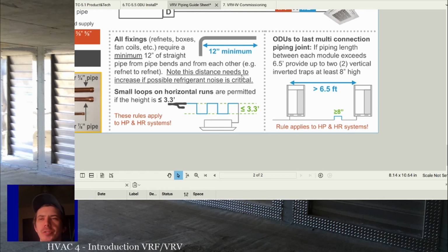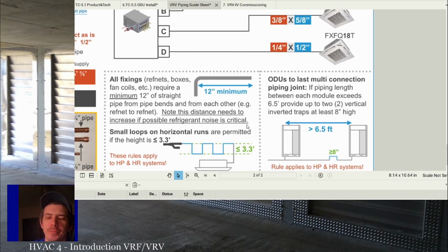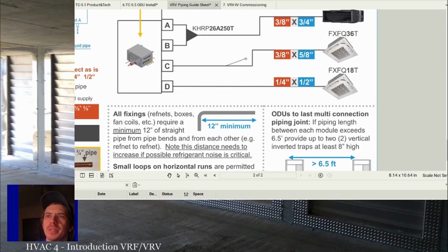And basically, when we say change of direction, we're talking about an actual fitting. If you're using a tubing bender to bend the pipe, you can be a little more relaxed. If you need a 45 and then another 45, but instead you bend the pipe in two directions and go that way, it's no big deal. But if you're going to bend two 90s with the tubing bender, even though it's a pretty long-turn 90, I would still try to get as much straight pipe as possible between those two bends.